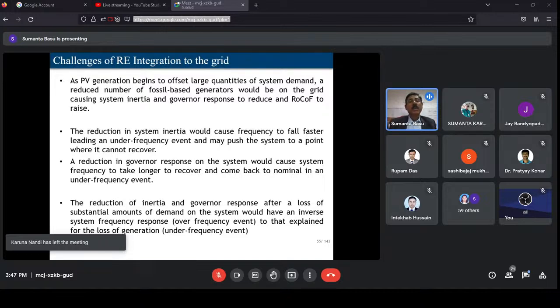So this PV generation doesn't have any inertia. As I told also, the more and more renewable energies penetrate the grid, the less and less the grid stiffness becomes. That means that any small disturbance, load disturbance, or frequency disturbance on the grid can perturb into a larger disturbance on the country-wise grid.